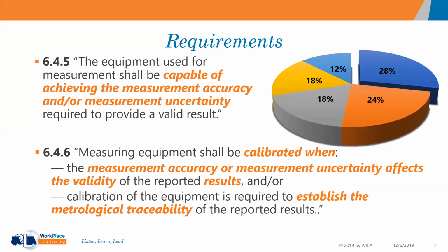Section 6.4.6, which I said piggybacks together with this clause, says that measuring equipment shall be calibrated when A, the measurement accuracy or the measurement uncertainty affects the validity of the reported results, which ties in wonderfully with what Karen brought up earlier, and the calibration of the equipment is required to establish metrological traceability of the reported results. So there have been nonconformances cited around this metrological traceability.